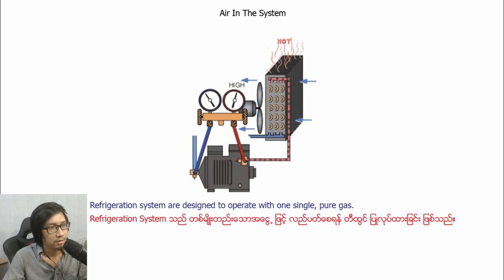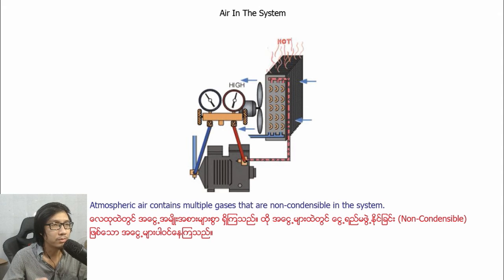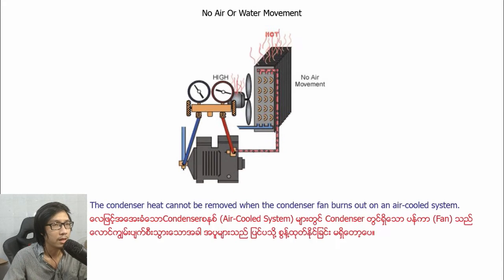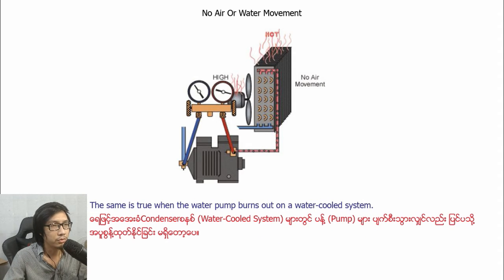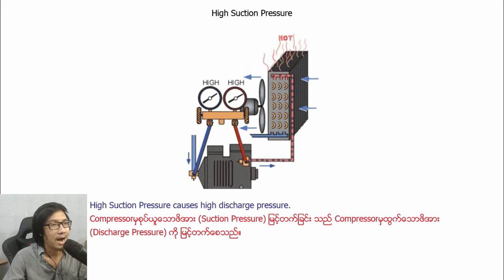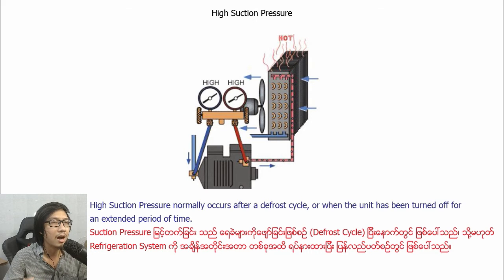Air in system. Refrigeration systems are designed to operate with one single pure gas. Atmospheric air contains multiple gases that are non-condensable in the system. No air or water movement. The condenser heat cannot be removed when the condenser fan burns out on an air-cooled system. The same is true when the water pump burns out on a water-cooled system. High suction pressure causes high discharge pressure. High suction pressure normally occurs after a defrost cycle or when the unit has been turned off for an extended period of time.